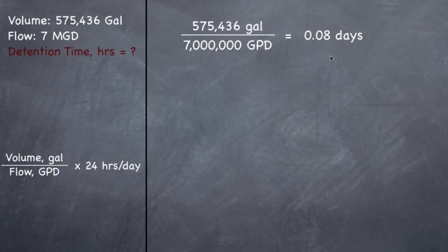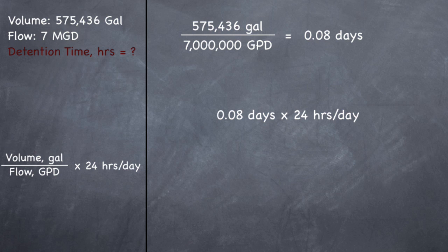So gallons divided by gallons equals 0.08 days. So if they wanted detention time in days, we could stop right here. But they want it in hours. So we need to go ahead and multiply this by 24 hours per day. So 0.08 days times 24 hours per day should give you 1.9 hours.